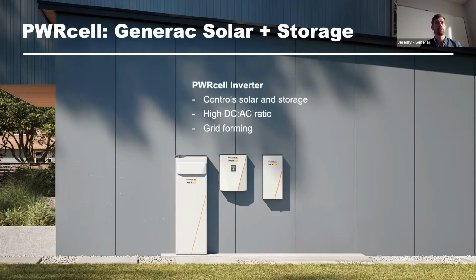This is the PWRcell inverter here in the middle. Unlike other systems that use a battery inverter or have inverters built into their batteries for AC coupling schemes, this is the only inverter you need in this system. So less stuff to install, and again, higher efficiency. It controls both the solar array and battery storage, and because you just have this one single inverter, with solar and battery all using the same DC bus format, this is a plug and play install. Not only fewer components to install, but a much easier configuration process as well.